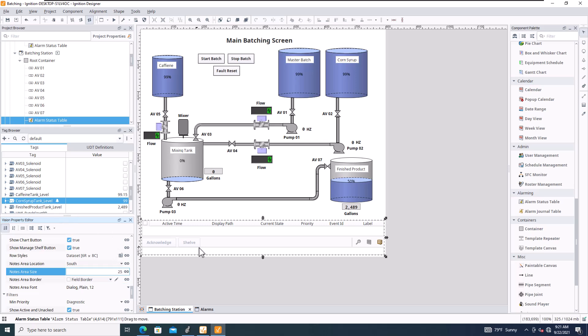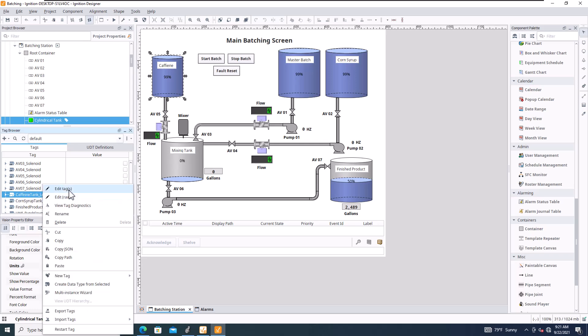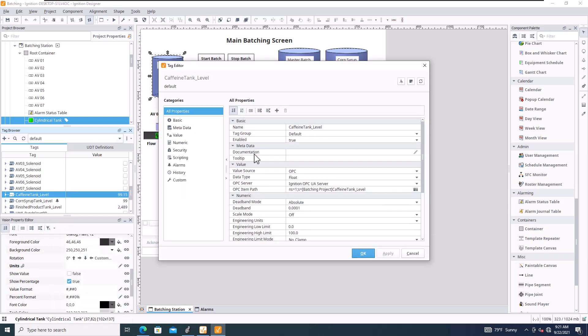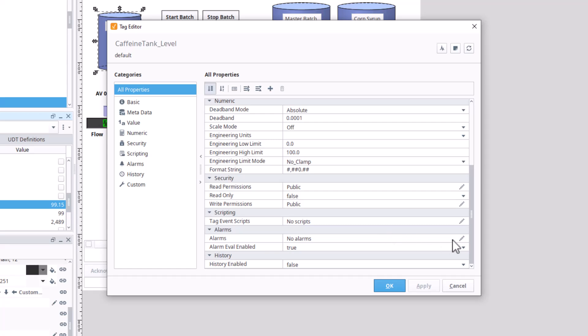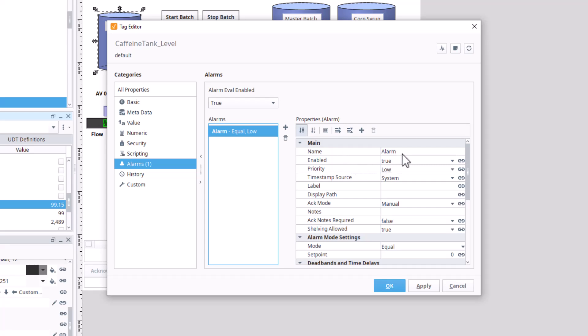I've already made a tag here, but let's make another alarm from the caffeine tank. Right-click the tag, go into properties, go to Alarms, and make a new alarm.